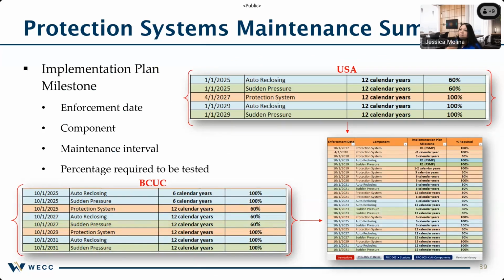Let's talk about tab number 2, implementation dates. These implementation dates and percentages differ between US and British Columbia entities. These are enforceable dates for components and the percentages required to be compliant. So for example, 100% of all sudden pressure components that have a maintenance interval of 12 calendar years, and again, this is based off the tables in the standard, need to be tested by 1/1/2029 for US entities and 10/1/2031 for British Columbia entities. So it's important to note that these dates are mandatory and it's not a suggested date. All components must be tested to be compliant. Next slide, please.